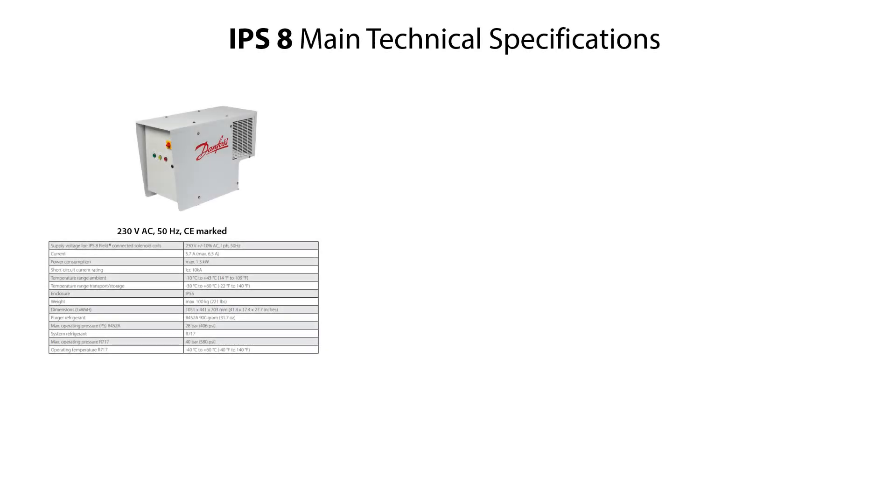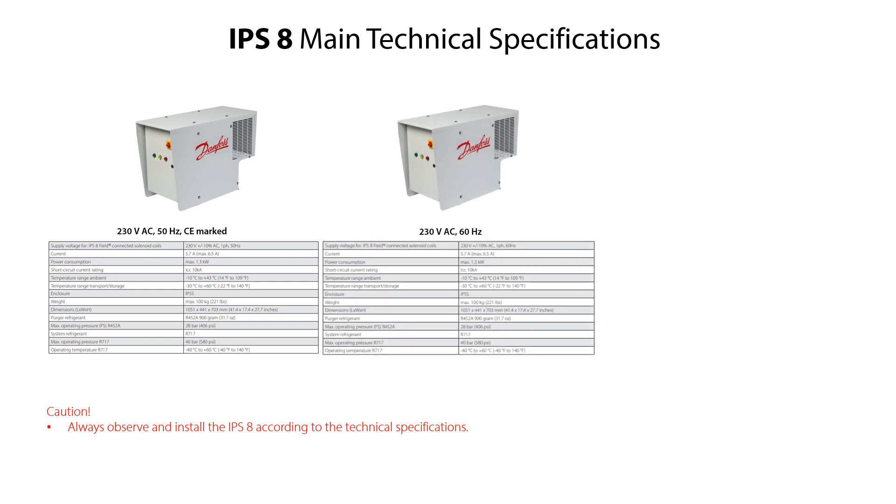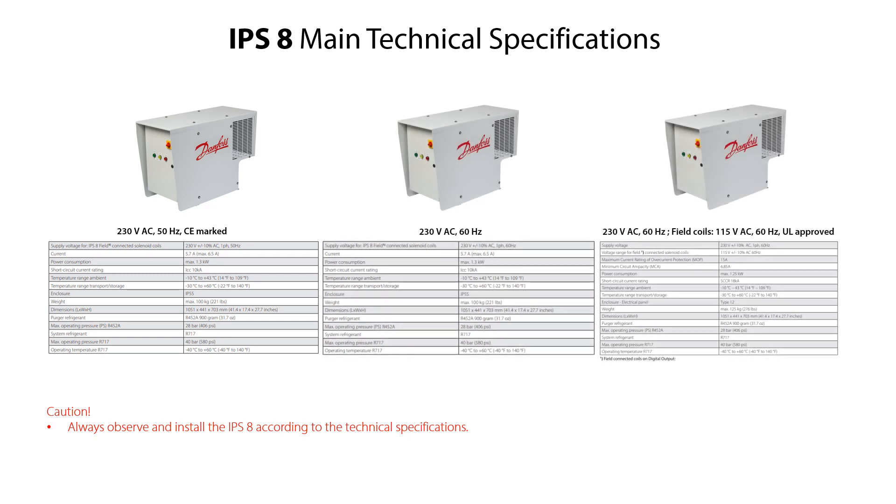Here you see the main technical specifications of the IPS-8. It is very important to observe and install the IPS-8 according to these technical specifications. Please note that there are three different IPS-8 versions available: a 230-volt AC 50 Hz, which is CE marked; a 230-volt AC 60 Hz; and a 230-volt AC 60 Hz with 115-volt AC 60 Hz supply for the field coils, which is UL approved. Most of the technical specifications are identical for all three versions.